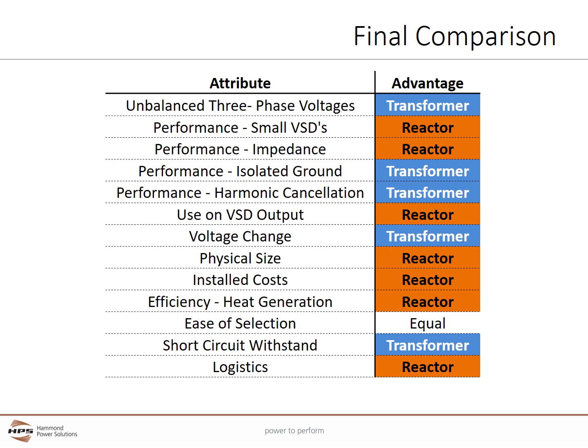In most cases, the user must weigh the advantages of either a reactor or a transformer for their application. Both devices are a vital part of an overall VFD system. Properly selected, both devices can decrease VFD failures and tripping events to save the user time and money.